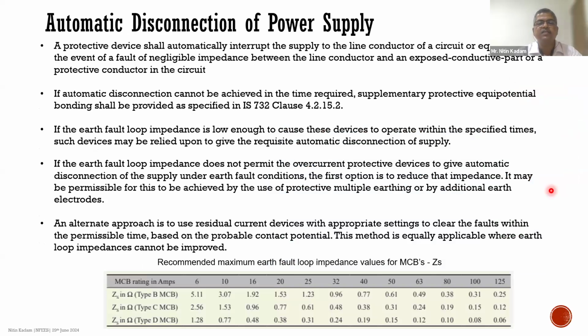Now, when you talk about the automatic disconnection of power supply, the protective devices to be used are the MCBs or the RCDs, which will automatically interrupt the power supply in case of earth faults. For that, the fault loop impedance values have to be according to the table given here. For each of the MCB types specified, the type B MCB, type C MCB, or the type D MCB, there are values specified in the code document, and these guidelines have to be followed. The fault loop impedance values have to be taken care of in the design stage itself, and they can be checked on site when the installations are being commissioned.